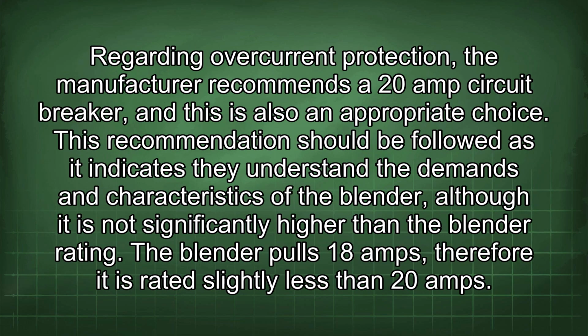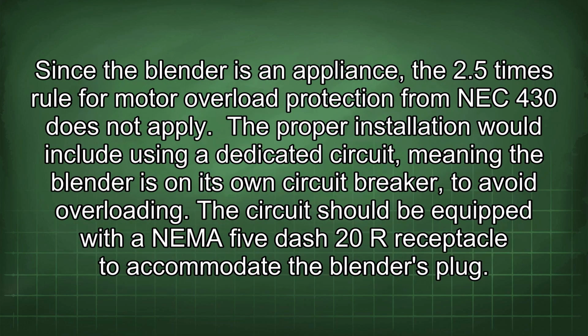Regarding overcurrent protection, the manufacturer recommends a 20 amp circuit breaker, and this is also an appropriate choice. This recommendation should be followed as it indicates they understand the demands and characteristics of the blender, although it is not significantly higher than the blender rating. The blender pulls 18 amps, therefore it is rated slightly less than 20 amps. Since the blender is an appliance, the 2.5 times rule for motor overload protection from NEC 430 does not apply.